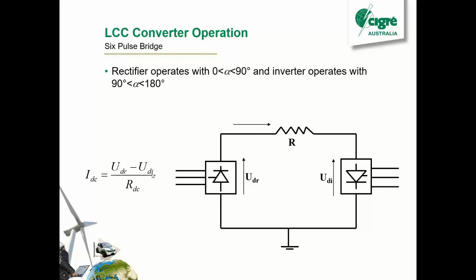But the way you build the converters is you actually put the inverter upside down to the rectifier. So the difference between the New Zealand scheme and in the North Island, all the thyristors point to the roof, and in the South Island, they all point to the ground. And then when you fire one as an inverter, the voltage is negative, so they cancel out. So you end up with, just for argument's sake, a positive voltage at the rectifier and the inverter that you can directly control.